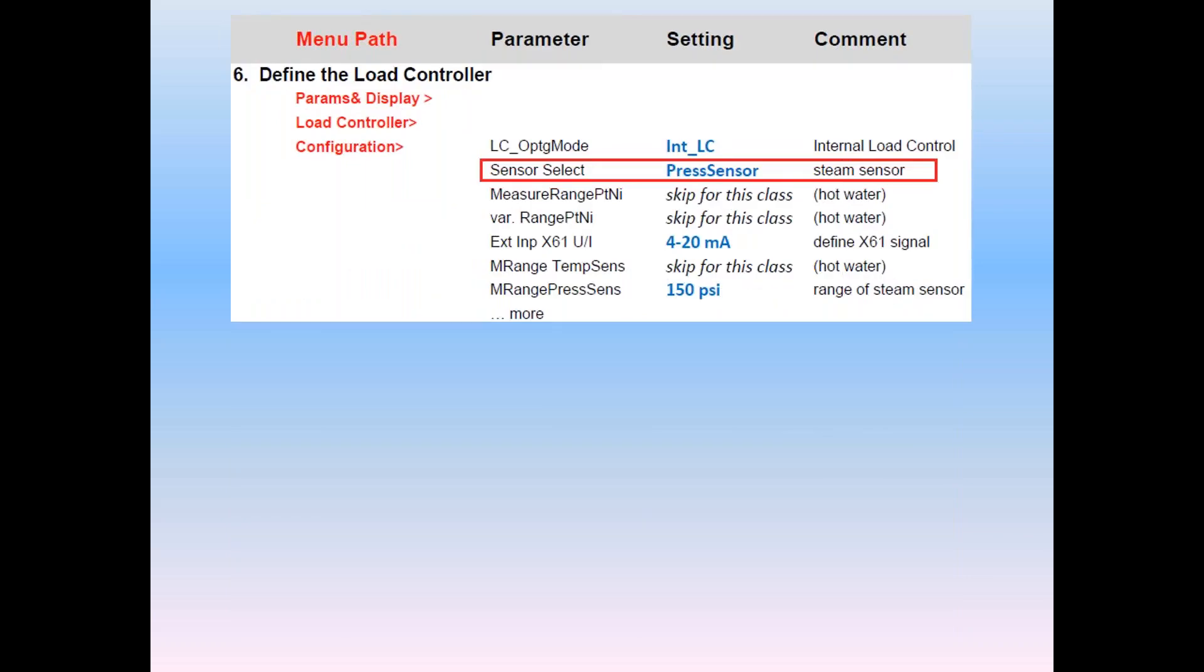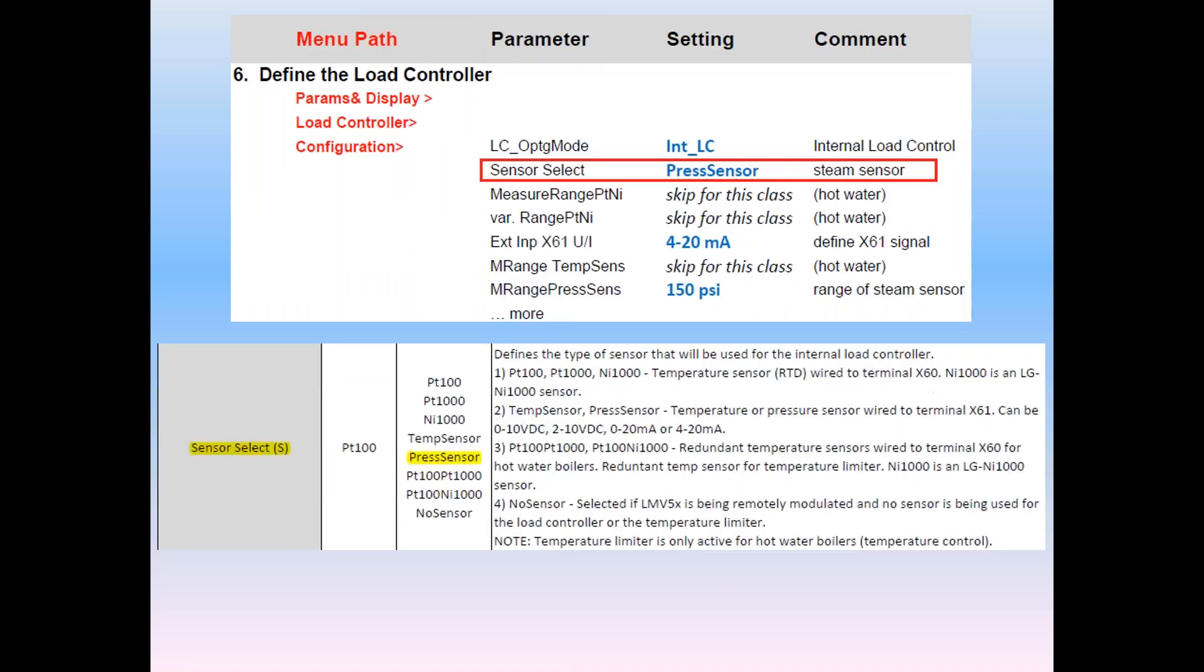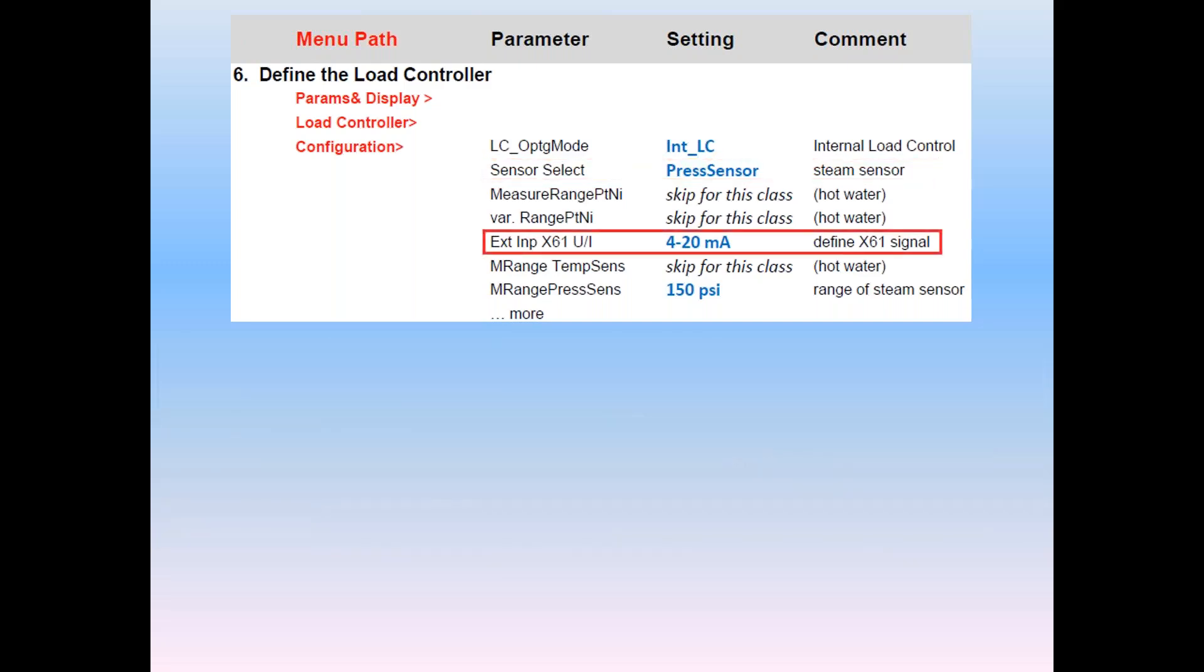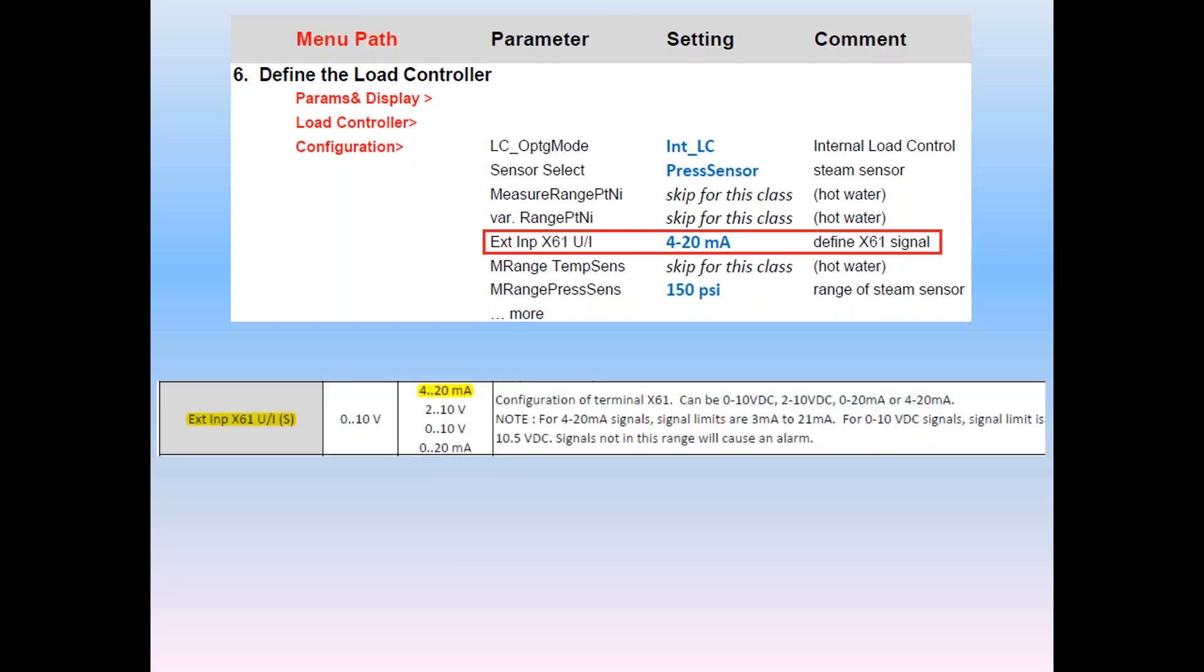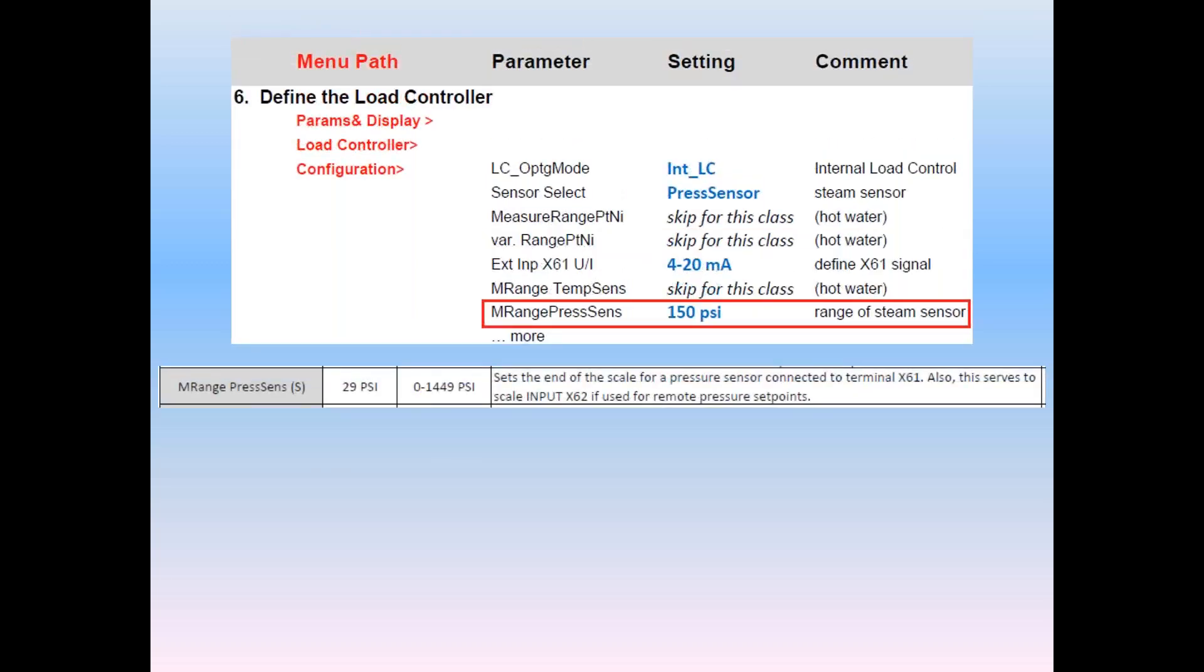Next, we select a sensor, and in this case, it is a steam sensor. Many other options are available. We must now define what type of signal is being used. Here, we use a 4 to 20 milliamp sensor and connect it to X61. Again, other choices are shown. Finally, M-range pressure sense, in this case a 150-pound sensor, scales the 4 to 20 signal so that it displays the proper pressure based on the sensor we're using on the job.